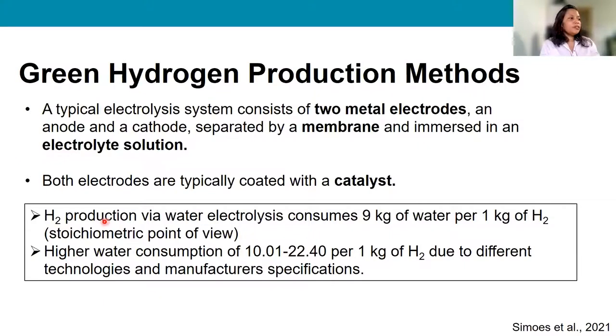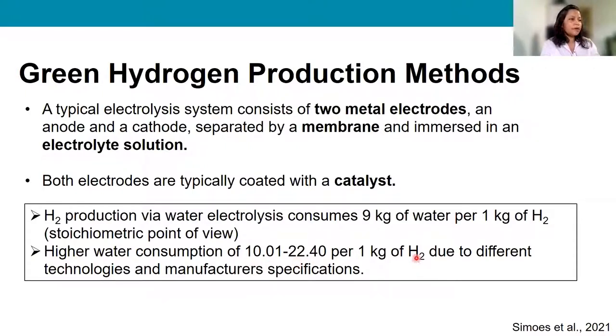From a stoichiometric point of view, for every kilogram of hydrogen you need 9 kg of water. In practice, however, it's much higher — ranging between 10 to 22 kg of water per kg of hydrogen — depending on the technology used and the manufacturer specifications.